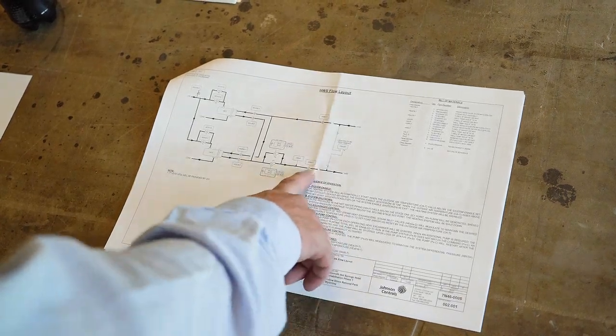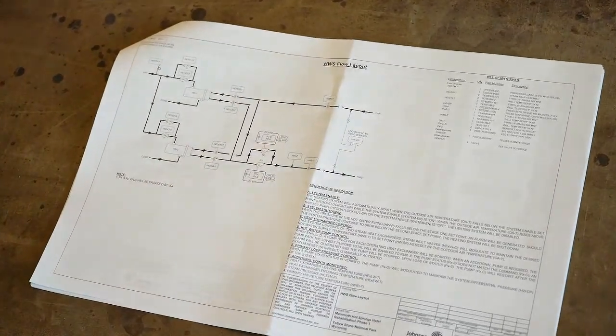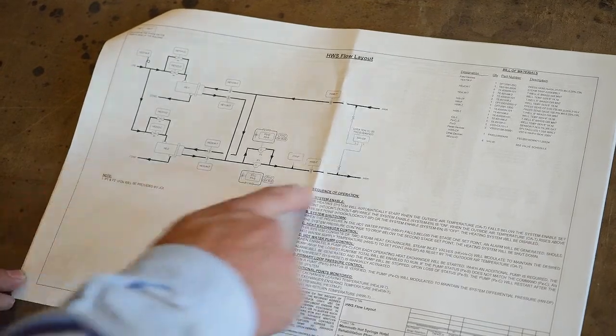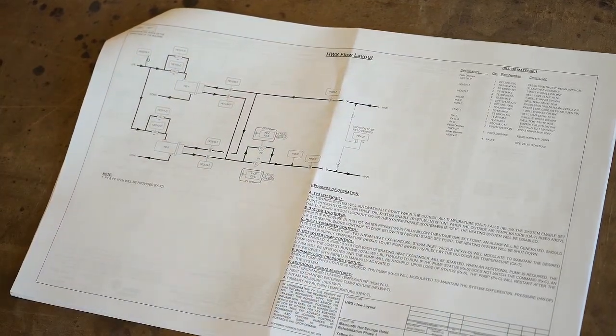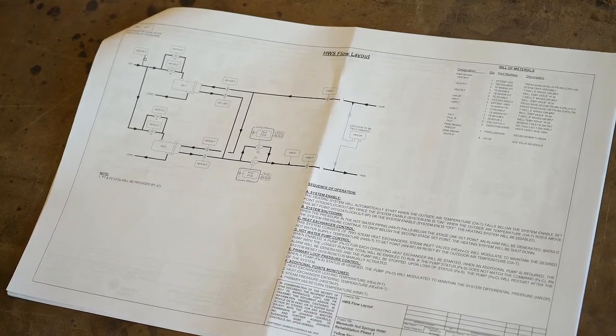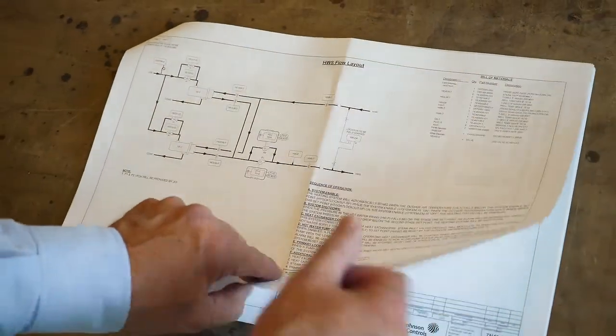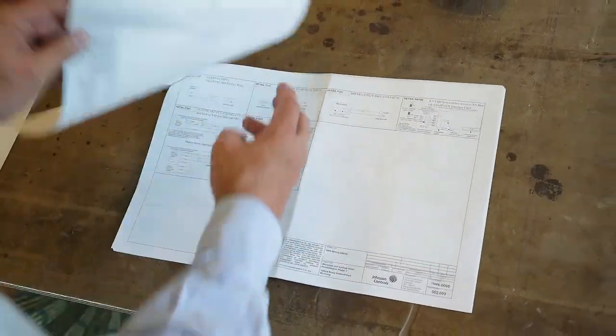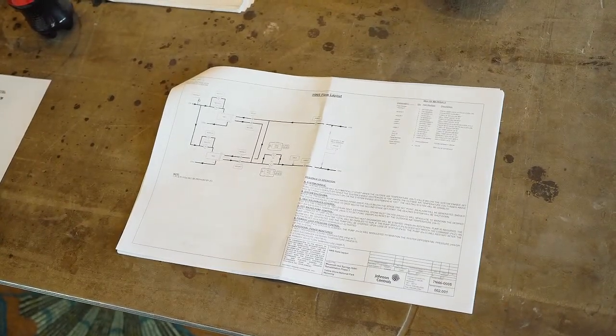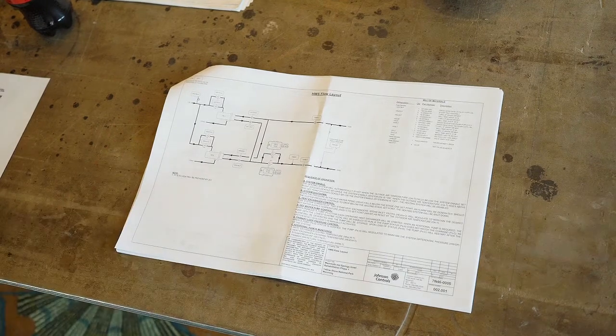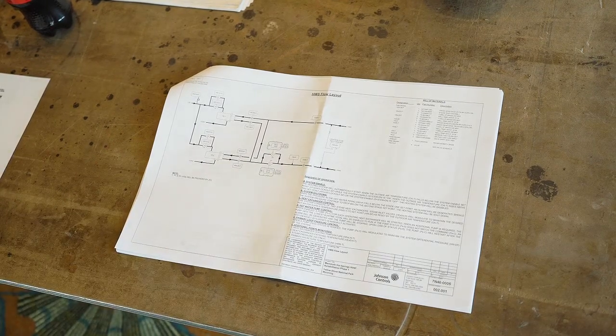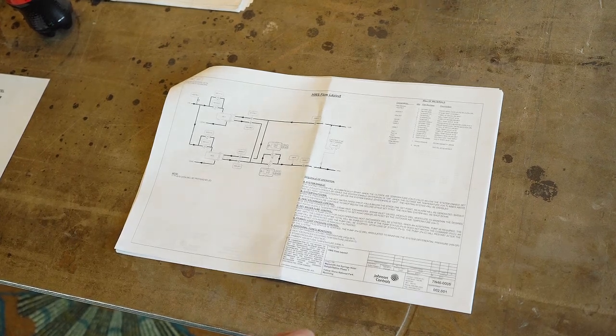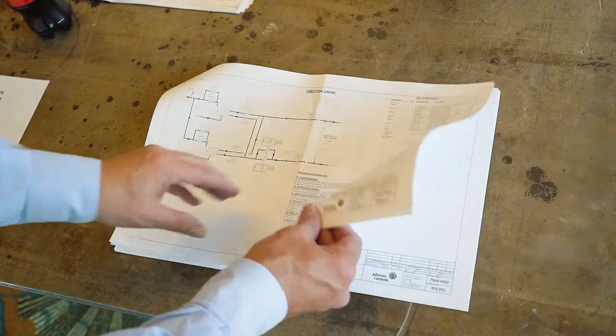We do have hot water supply and hot water return temperature sensors in here too. And the graphics on the front end look pretty much like this here. A little nicer colors, but basically the same layout. Okay. And we'll go through and point out where all those locations are. Where's the location like for the outdoor air temperature sensor? Is it out on this, you know, trying to figure out what end of the building? You probably know where that is from. It's usually on the north side of the building, right? It's out by these condensing units. Yep. Okay. So if we pack it over with snow, like we're gonna do those conditions.